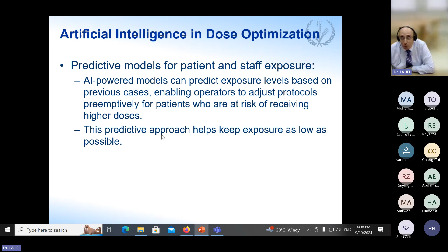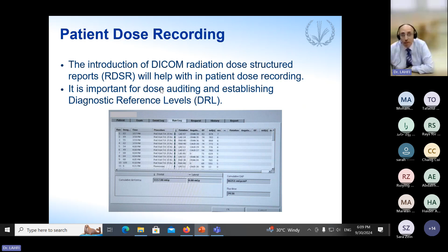Also, patient dose recording is very important. Nowadays, with DICOM, we have the RDSR, the radiation dose structured report, which helps with patient dose recording. These reports are important for dose auditing and also for establishing the diagnostic reference levels. Here we can highlight the role of the medical physicist in supervising and auditing the patient doses from these dose logs.